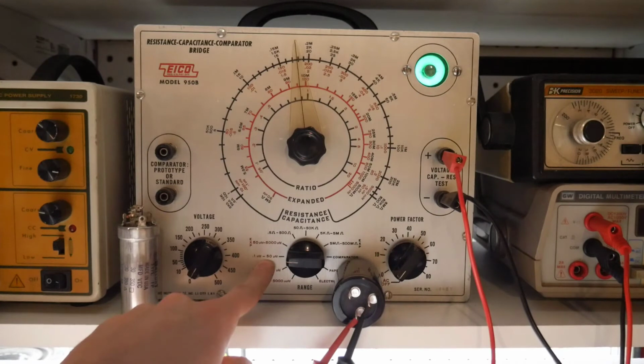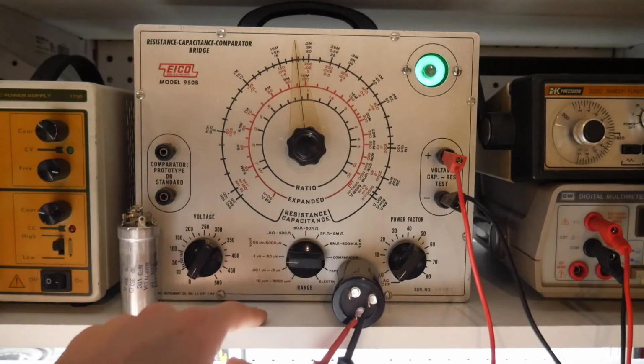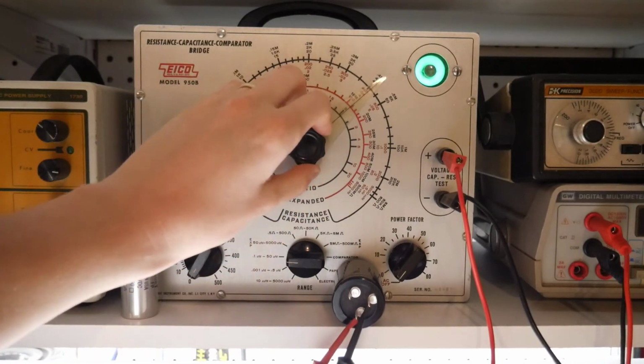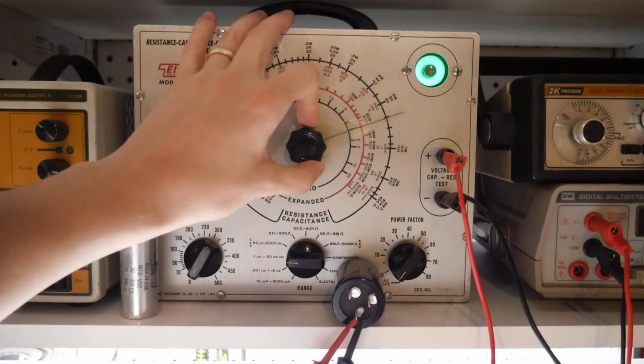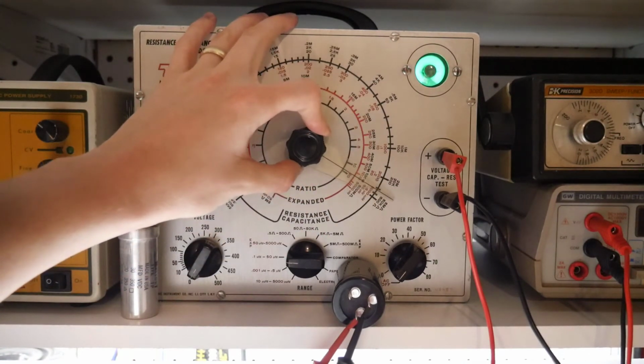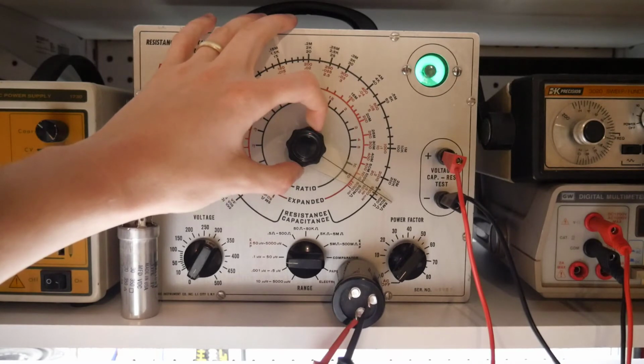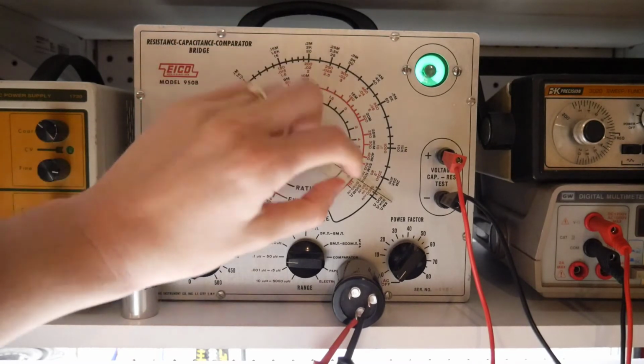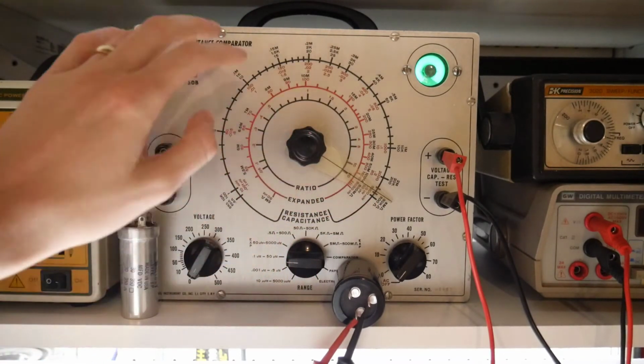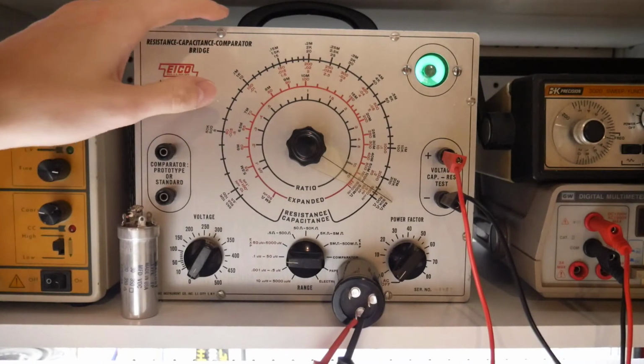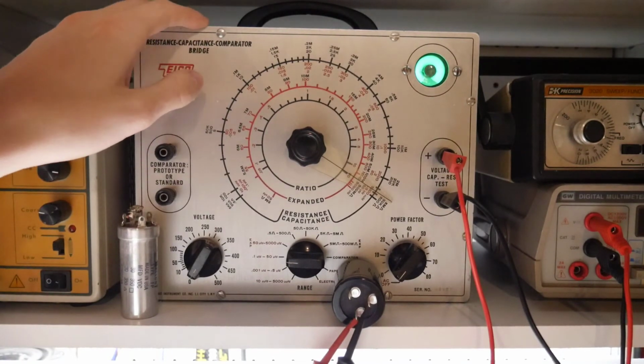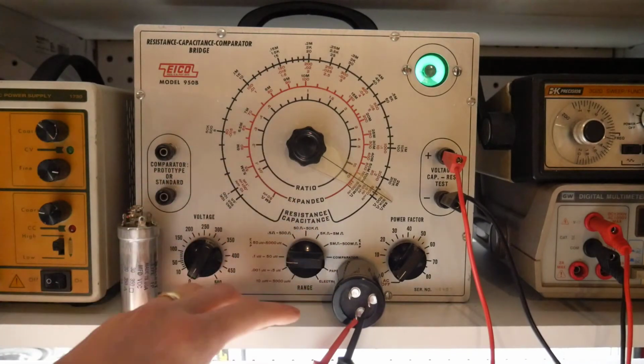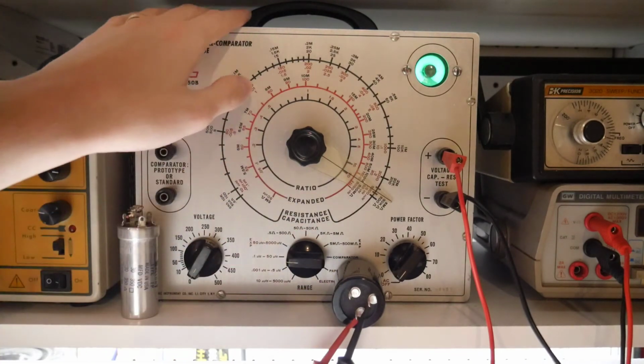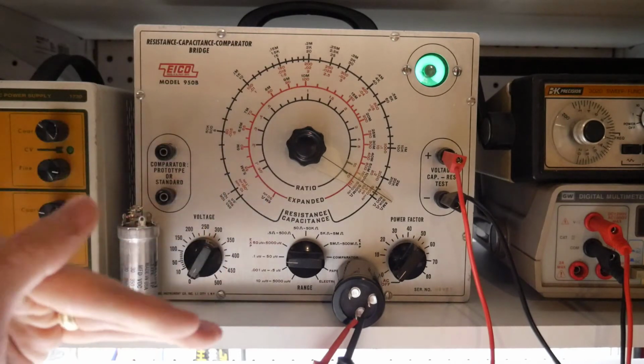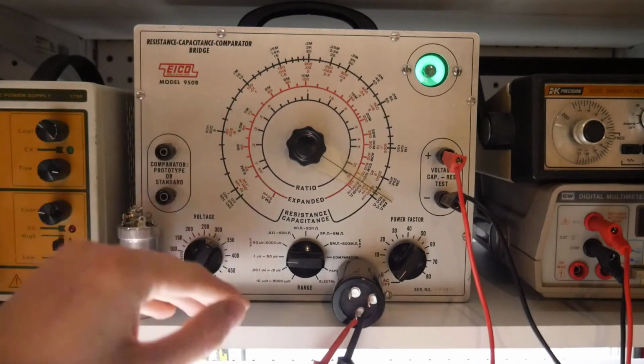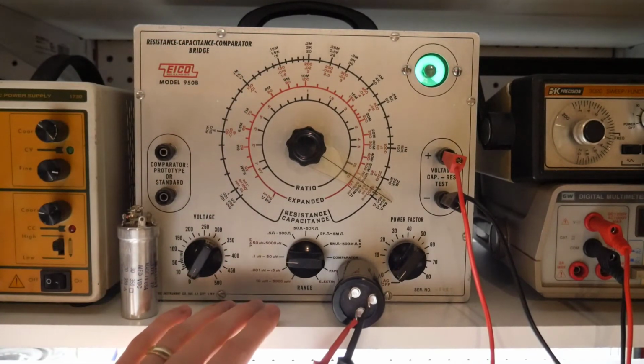We're set here to 0.1 to 50 microfarads, so we're going to confirm the capacitance is in a good range. You could say it's good about there, not quite at 40 — I'd say it's 30, 35, 36, 37 or so microfarads on just this one side. I'm only testing one side to prove the concept, but capacitors generally run high in value, and that's okay. That'll work just fine for what we're trying to do.